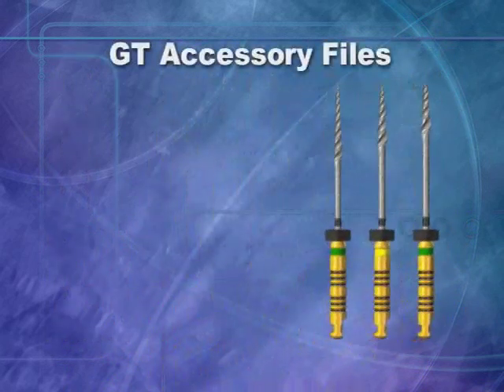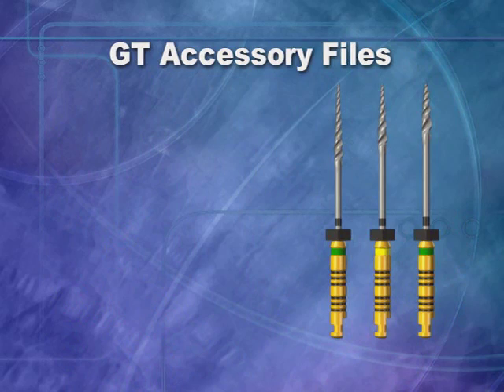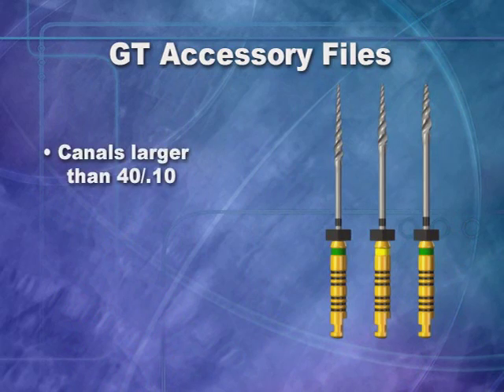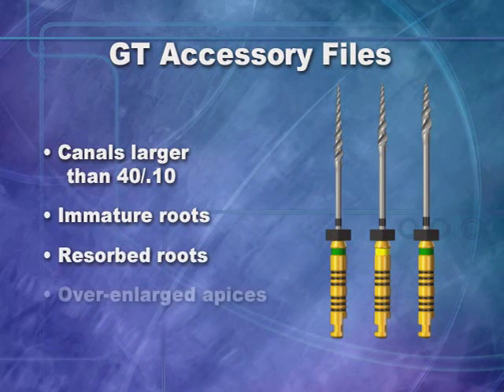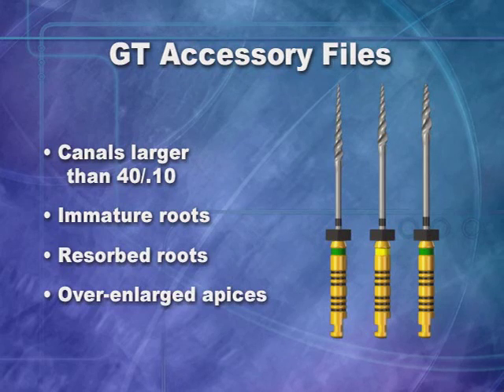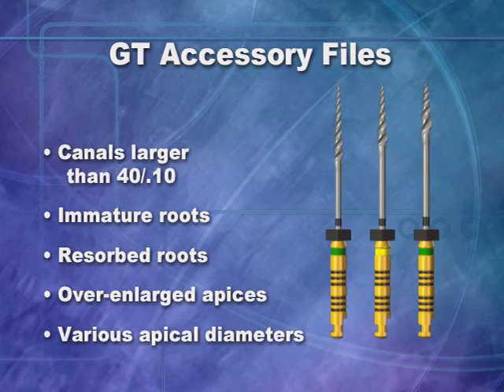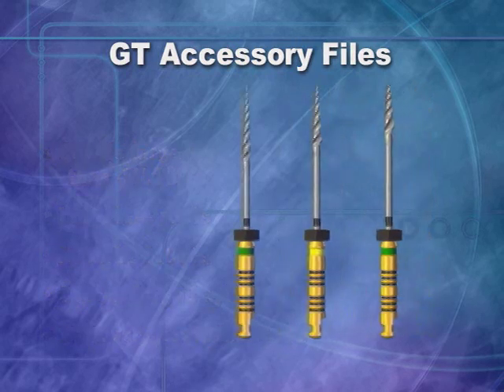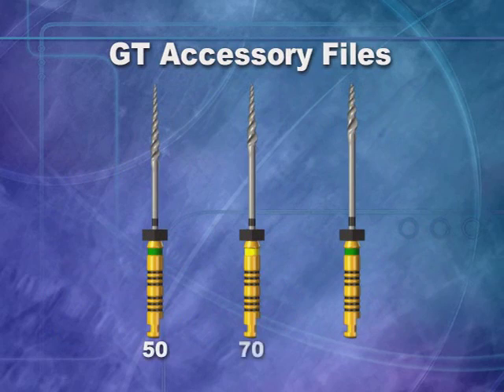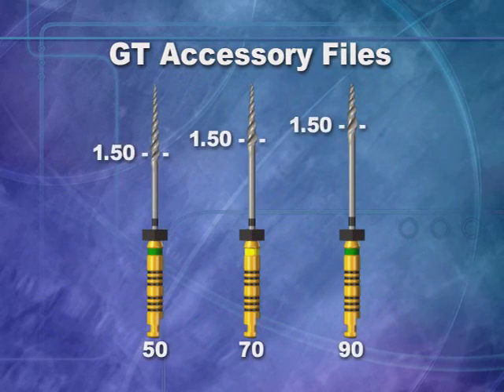Additionally, three accessory files complete the family. GT accessory files are needed in canals larger than a 40.10, and in large roots with immature, resorbed, or previously over-enlarged apices. These files can be used long or short to accommodate variations in apical diameters. All have a .12 taper. The tip sizes are 50, 70, and 90. The maximum flute diameter of the accessory files is 1.5 millimeters.